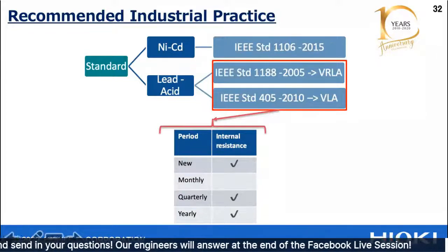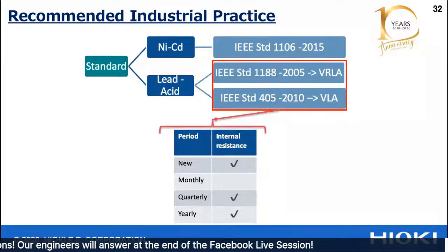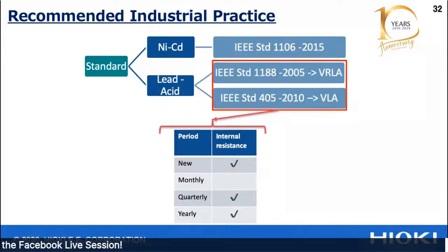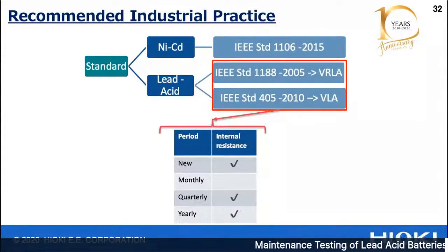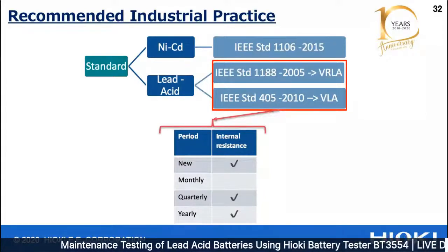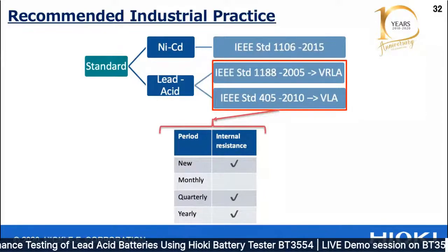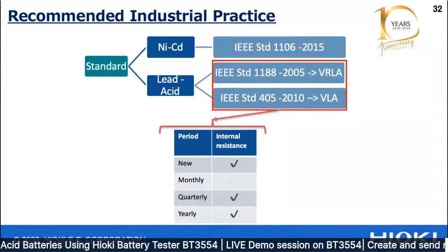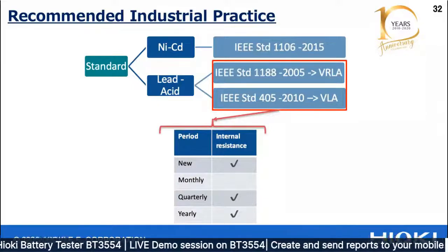The maintenance routine is just for reference and depends on each company's policy, but it's good to carry out IR testing for new batteries and subsequently quarterly or yearly, depending on the status of the battery. In these standards there are other types of testing, such as float charge current and capacity testing, but IR testing is applicable for the BT3554.